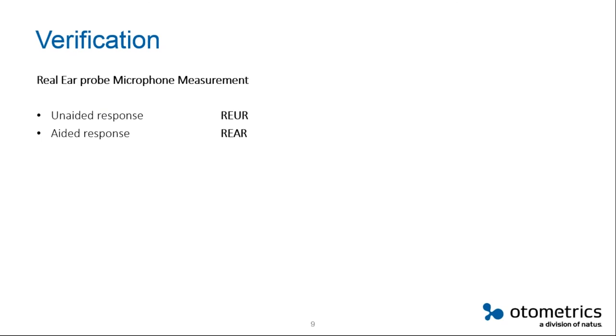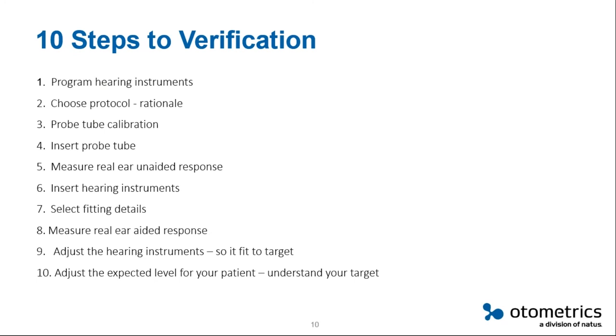Additional time is required for the fitting process, but I think we actually save time when doing verification. In a very simplified way, we need to measure the non-aided response and the aided response — that's what we have to do. We need to understand that all our customers don't have the same needs, so meeting the target means meeting the target for this patient. If we look at the 10 steps, the first is to program the hearing aid, which we have to do whether we are using verification or not.